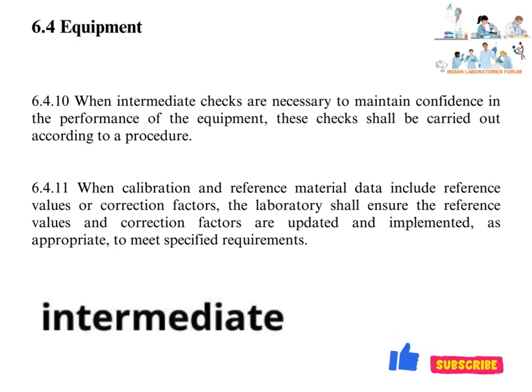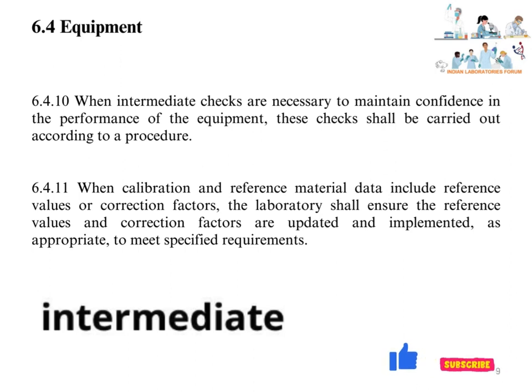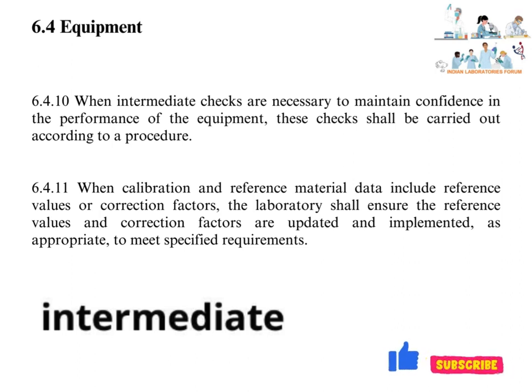When intermediate checks are necessary to maintain confidence in the performance of the equipment, these checks shall be carried out according to a procedure. An intermediate check is the performance check of equipment in between two calibrations. The laboratory should have a procedure on how to perform the intermediate check, what the acceptance criteria are, and a defined template for recording intermediate check data.